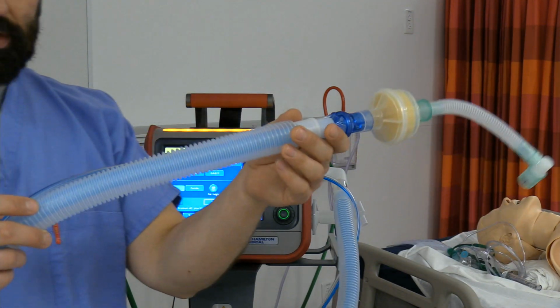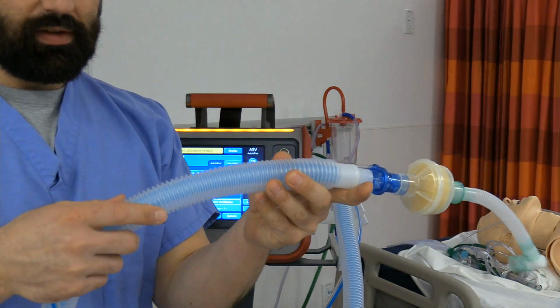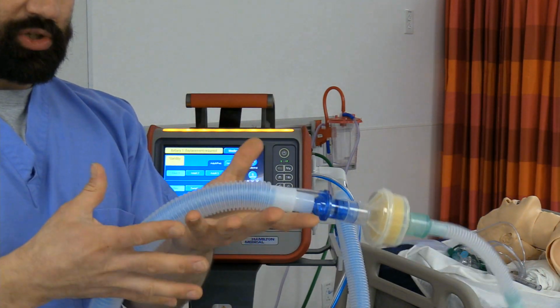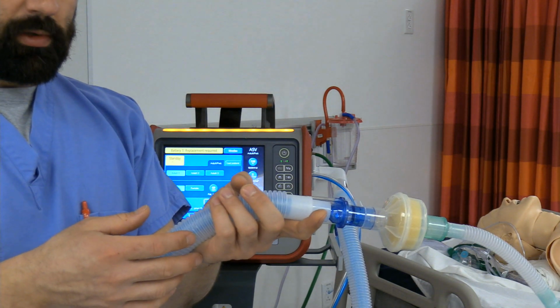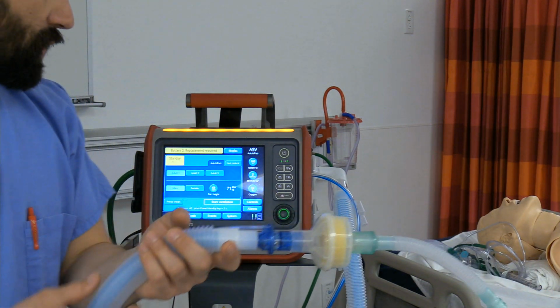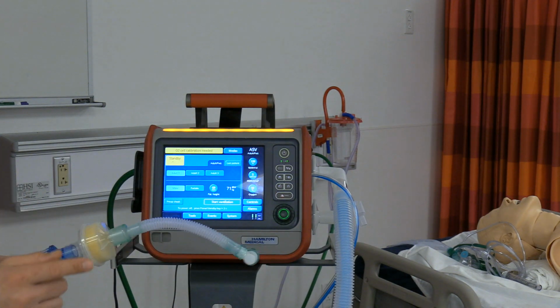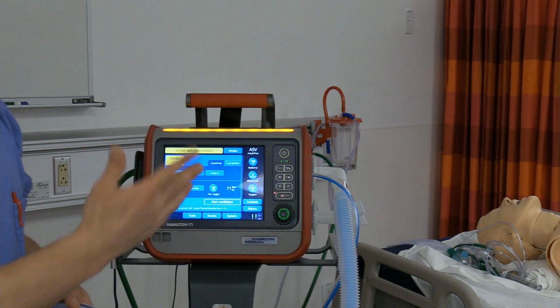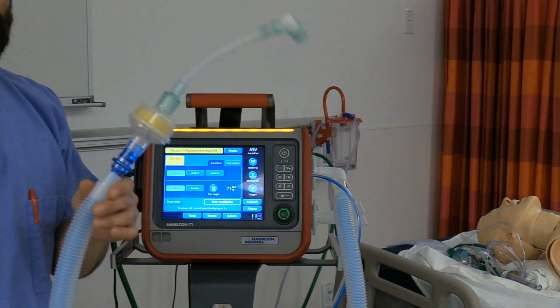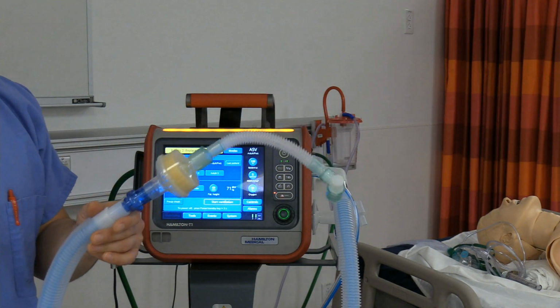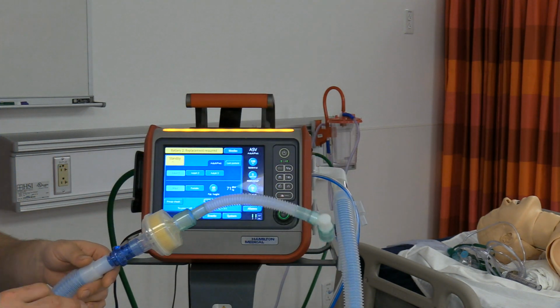When you think about this tubing itself, it's not made out of a hard material, so as it pressurizes, some of the volume we hope is going to the patient is going to be lost in that circuit compliance. So by doing this test, I'll tell you exactly what specific test, it's going to make sure this vent's ready to roll, and it's going to make sure our values are accurate and everything is working the way it should.